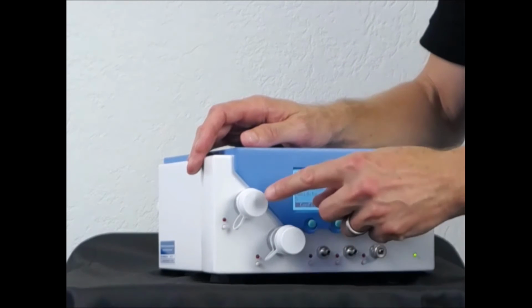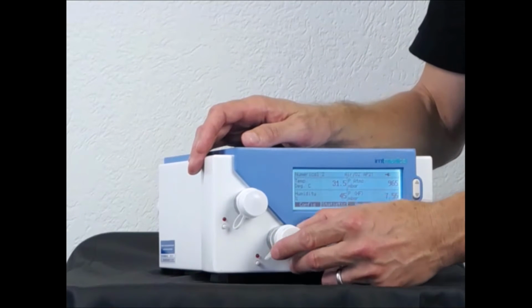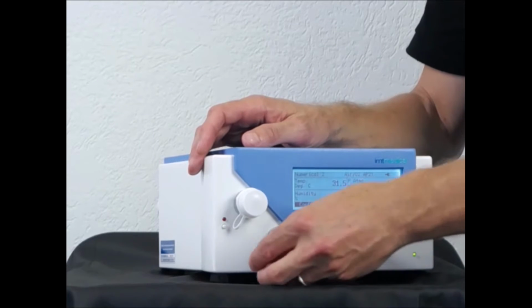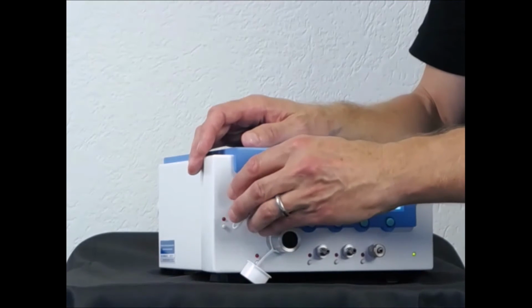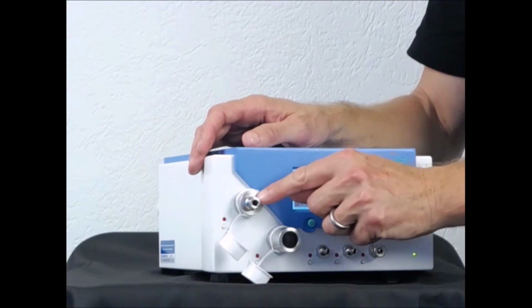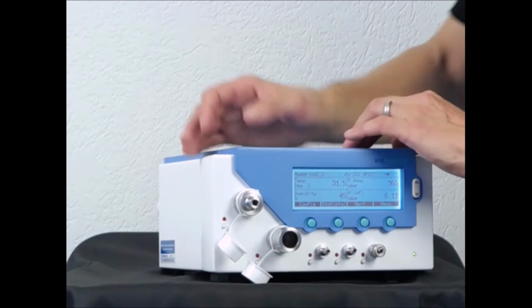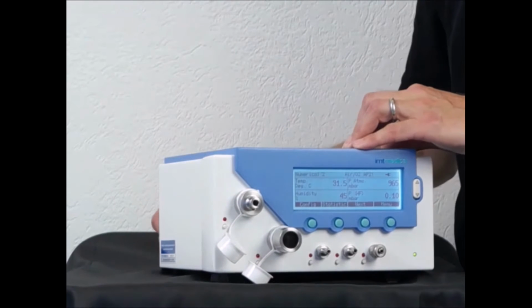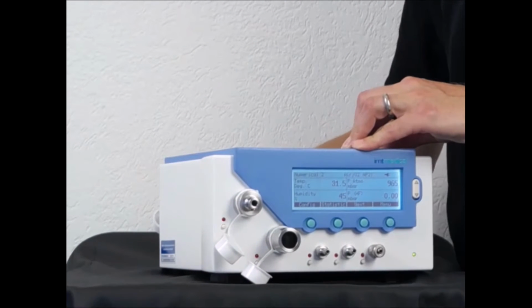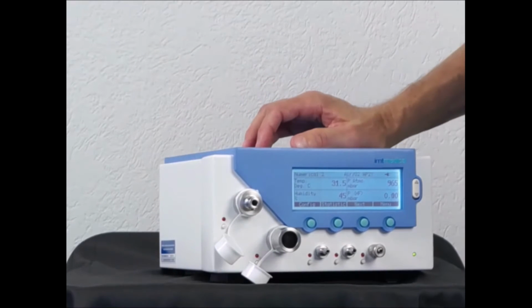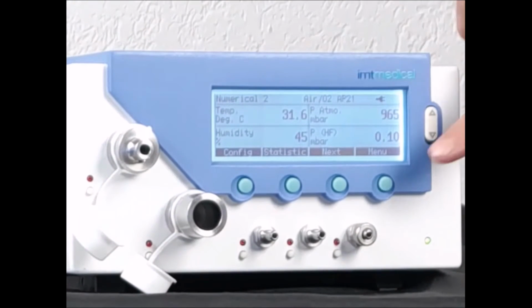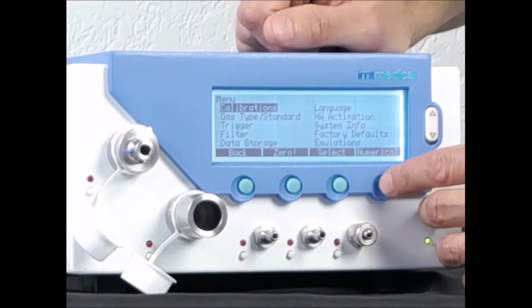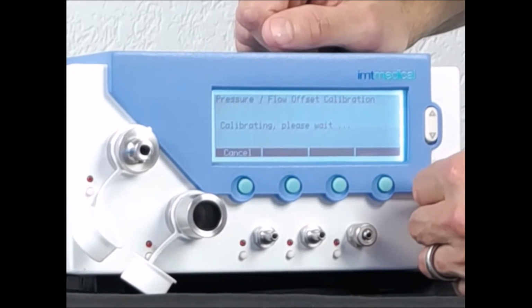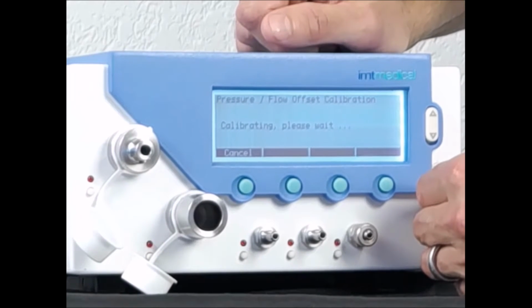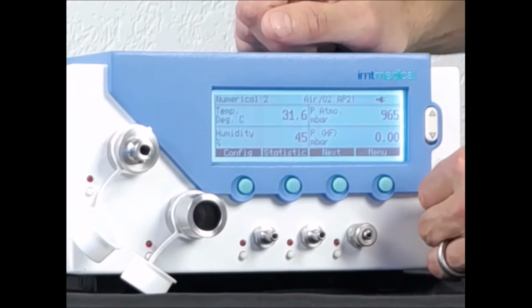It is now protected with these white caps. This is good for transport to avoid any dust going into the sensitive measuring device. I open both channels, the low flow channel and the high flow channel, and I also do the same in the rear. Then I perform the zero operation. It is here in the menu, zero, and it takes a few seconds, and then all the measurements are zeroed.